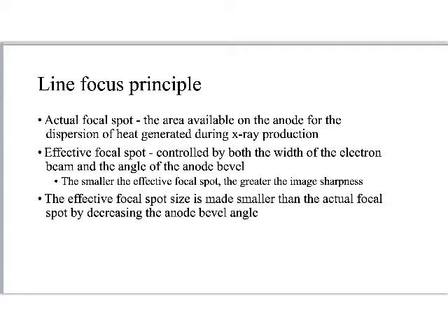What gets a little bit confusing is that when we're talking about this as technologists and adjusting focal spot size, what we're really talking about changing is the effective focal spot size. That effective focal spot size is produced by giving the anode an angle. The effective focal spot size is controlled by both the width of the electron beam and the angle of the anode bevel. As a general rule of thumb, as we decrease the effective focal spot size, we will increase image sharpness. We'll decrease that effective focal spot size by decreasing the anode bevel angle.